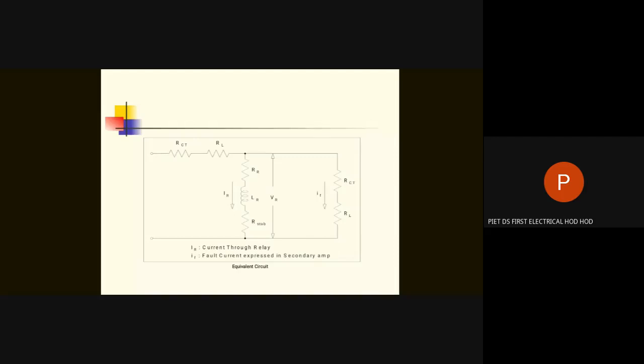You have to ask the relay manufacturer what the resistance of the relay is. Based on this, you can always find the value of R stab by the formula presented on your screen. It is coming from a simple Ohm's law. So R stab is equal to IF into RCT plus RL, divided by IS. IS is the setting of the relay.